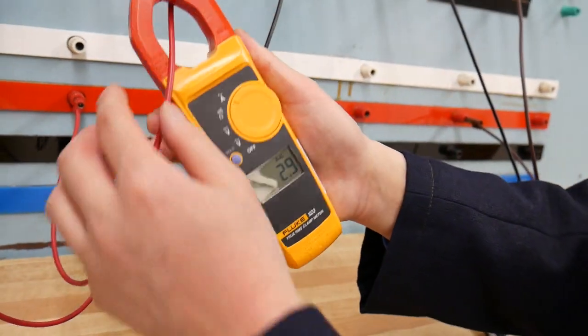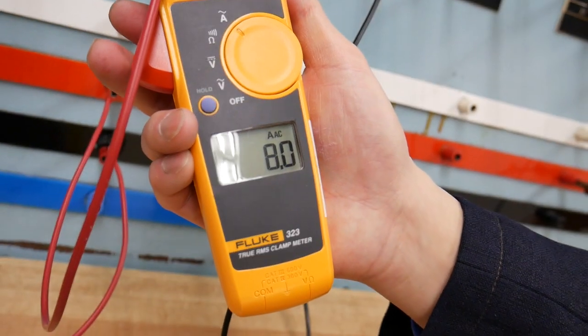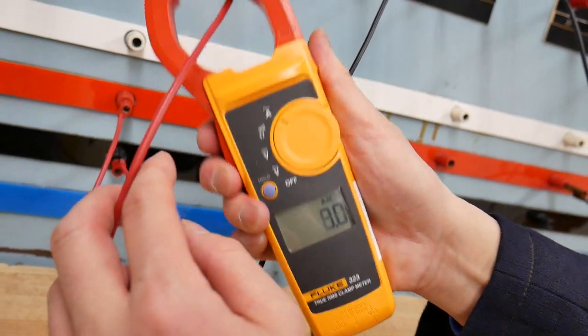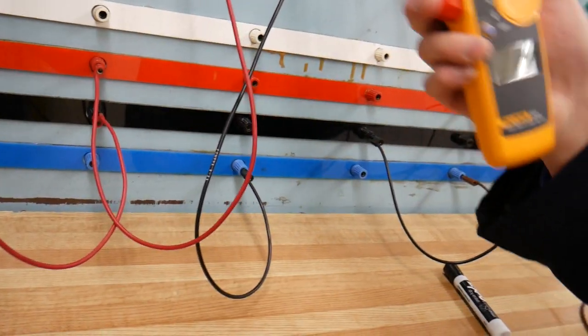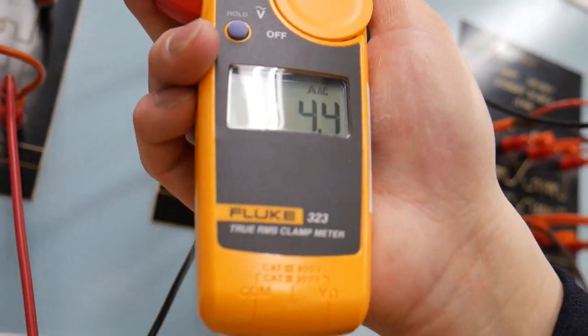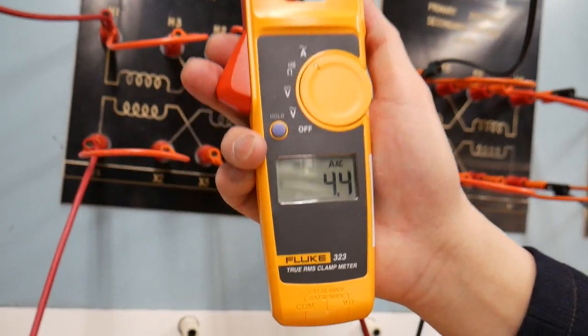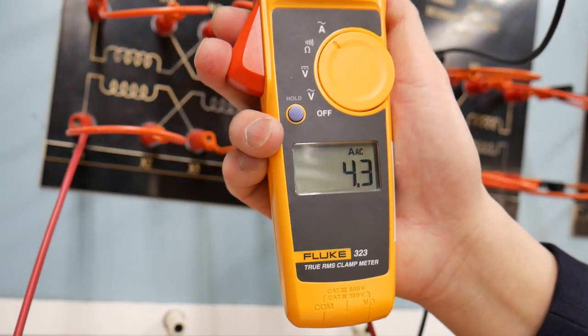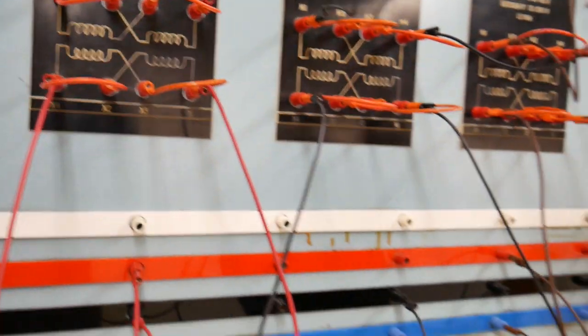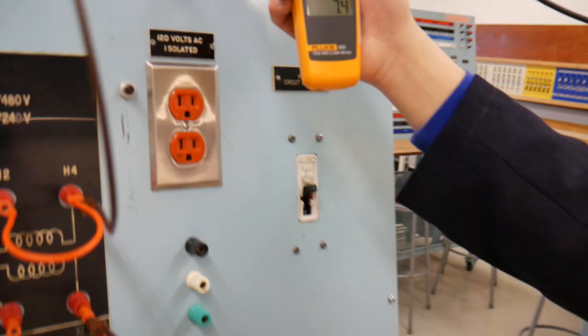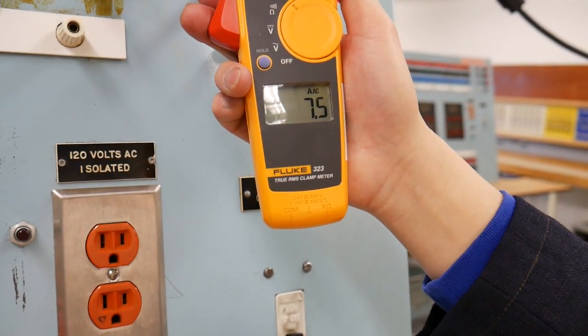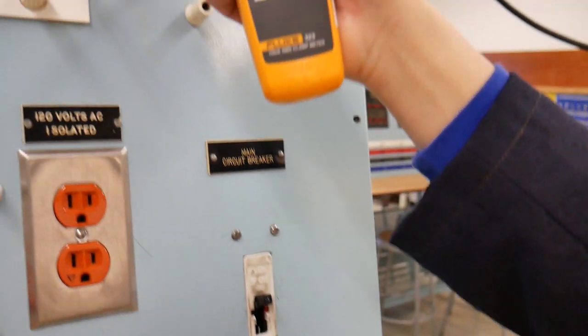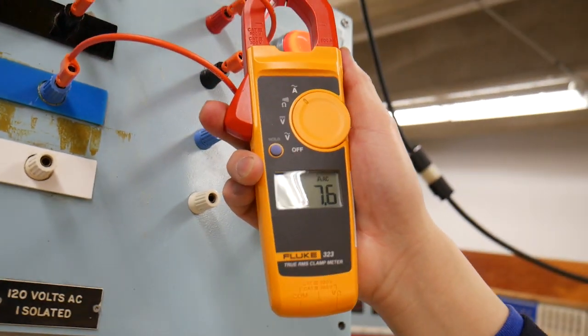Now I'm going to measure my transformer phase current, it's 8 amps. Now the primary phase current, it's 4.4 amps. I can measure across different transformers and it will be the same 4.4 amps. Now I'm going to measure the primary line current: 7.5 amps, and 7.6 amps.